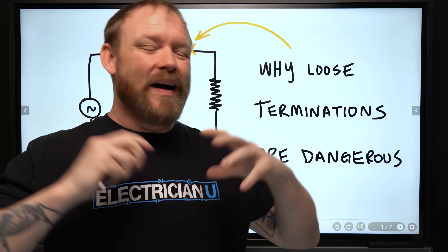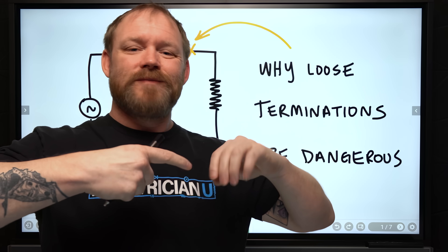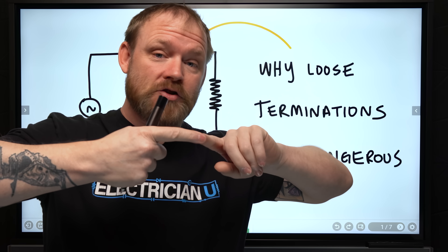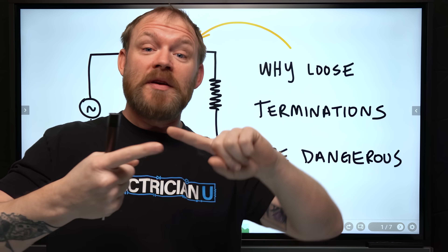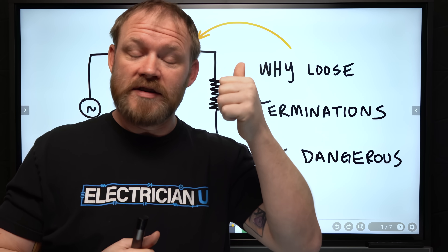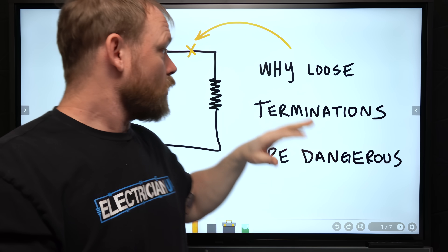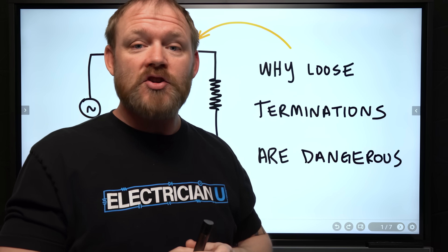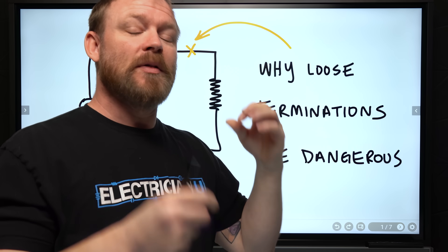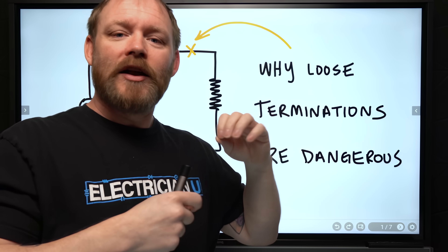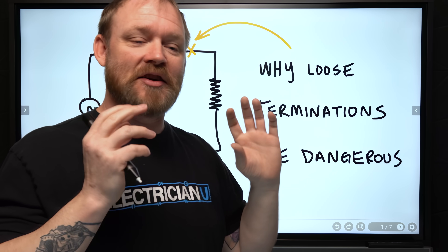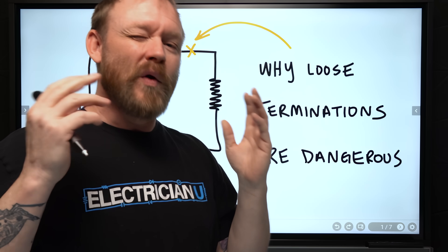If you have a failure point in a circuit — like a termination, a wire nut that comes a little bit loose — it's losing its connection, which means compared to a solid connection, there's less contact, which ends up being more resistance and less current flow. When we have a high-resistance termination, we have a whole bunch of heat that builds up. But the graph of how this works would actually surprise you.